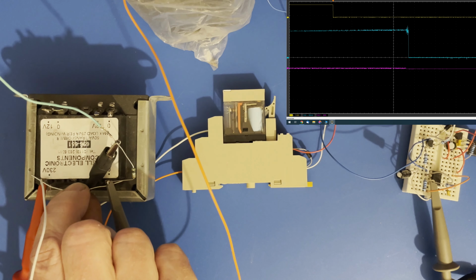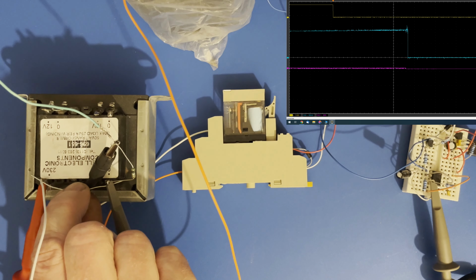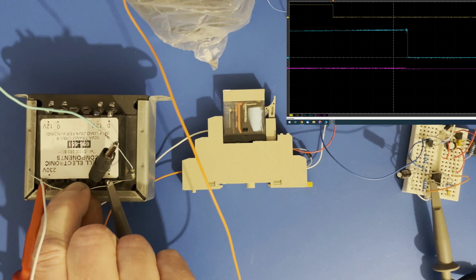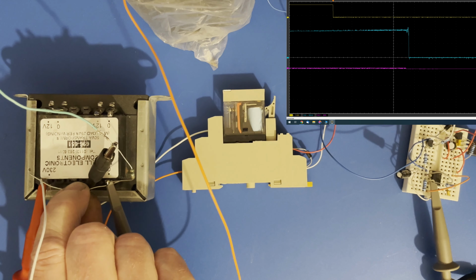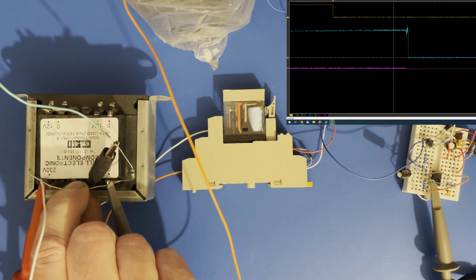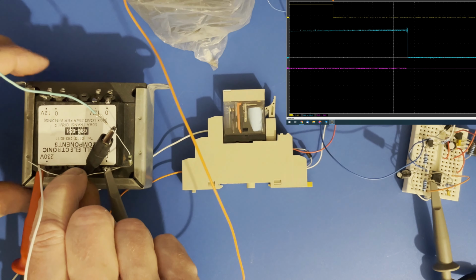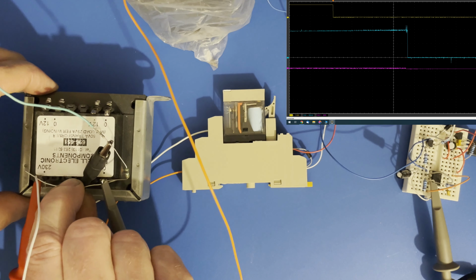I mean, the ramp up's changed because this core's now getting magnetised because all the current's in the same direction all the time. So it's affecting how it ramps up. It is still ramping up, it's just a different curve. So the bit you can see as it is looks flatter. But you can see with that, there's no high voltage spike, everything's nice and clean.